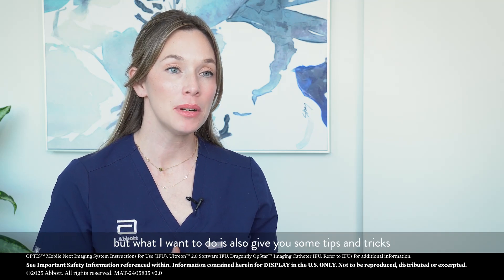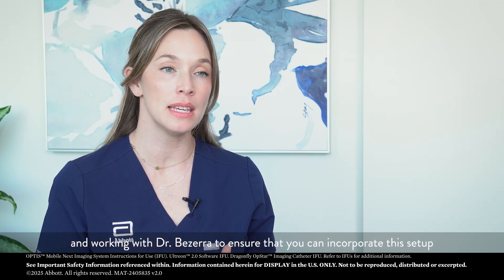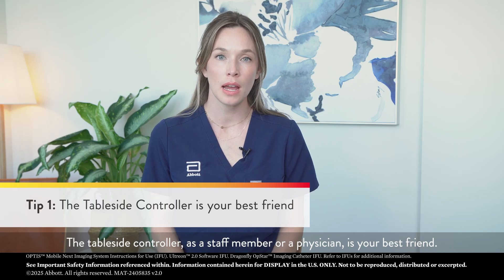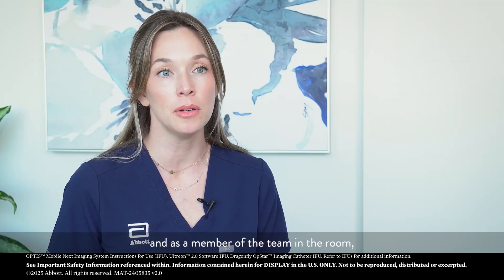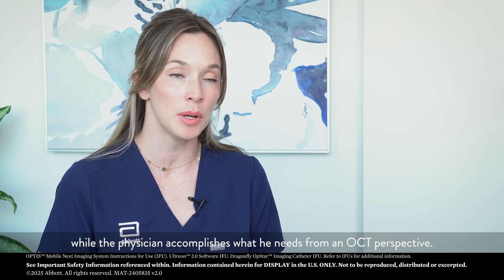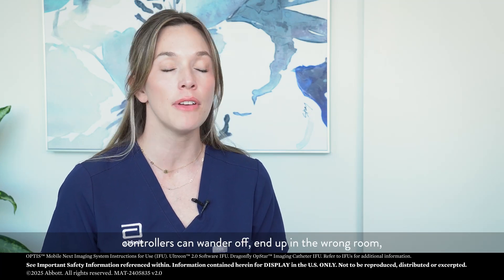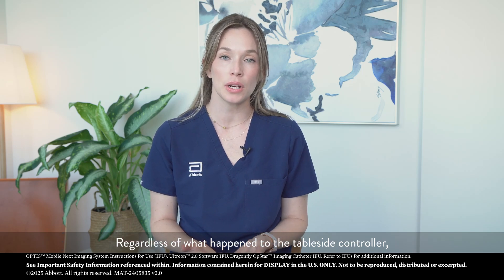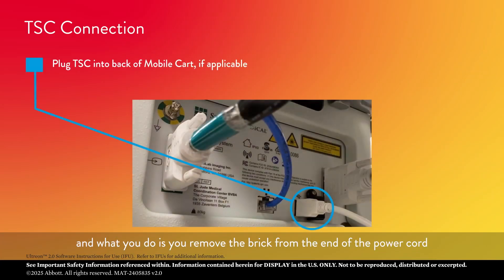We've covered a lot of steps in the setup process, but I also want to give you some tips and tricks from my time in the field working with Dr. Bezzera. The first tip is about the table side controller — as a staff member or physician, it is your best friend. As the physician, it lets you operate the software independently. As a team member, it allows you to attend to other patient needs while the physician accomplishes what he needs from an OCT perspective. With mobile systems and busy labs, table side controllers can wander off or end up in the wrong room. If you ever need to use one quickly, you can always borrow from another room — remove the brick from the end of the power cord and plug it directly into the USB port on the back of the mobile system.